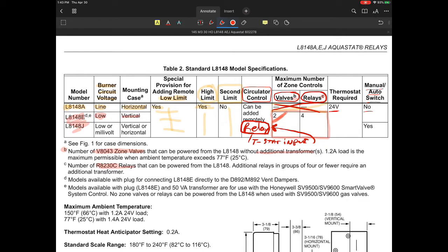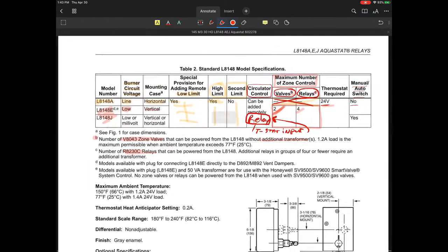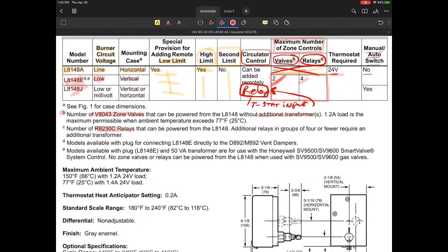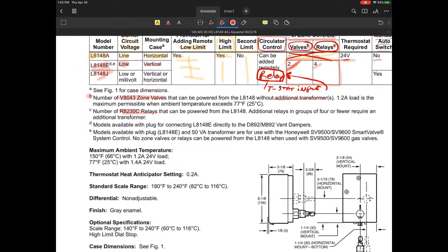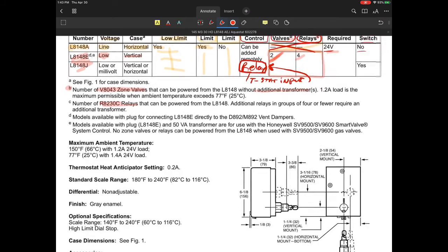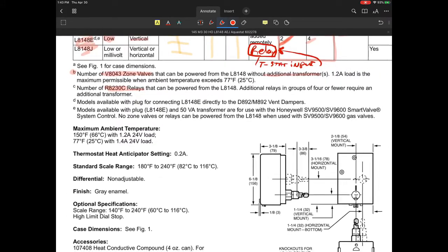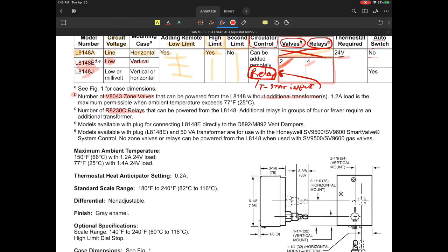What they're getting at is they make a specific zoning relay or a pump relay that they're identifying as an R8230C relay, and they're saying up to 4 of those relays can be powered from the transformer that's internal in the control. That will allow the system to function with up to 4 zones that would be individual zone pump applications. And again, the same 24 volts that we had talked about earlier. So that's really a big one on here.